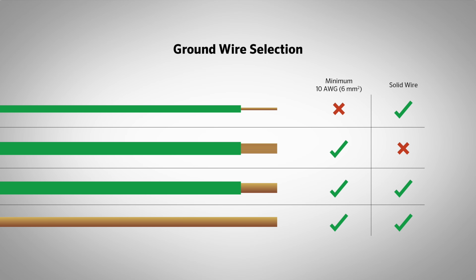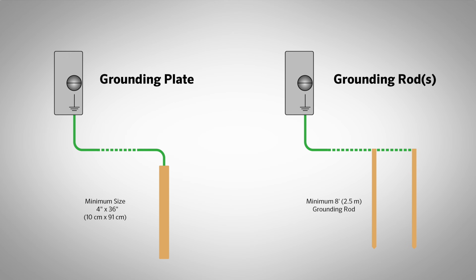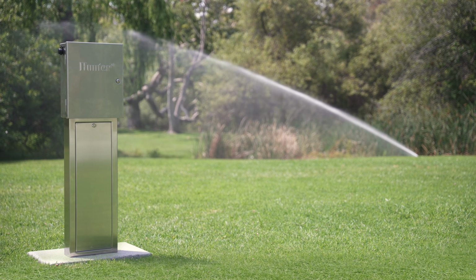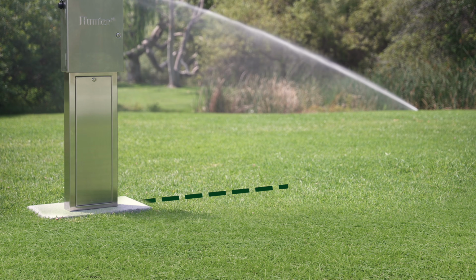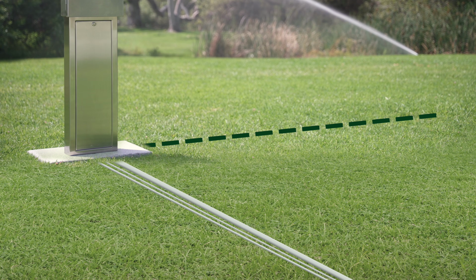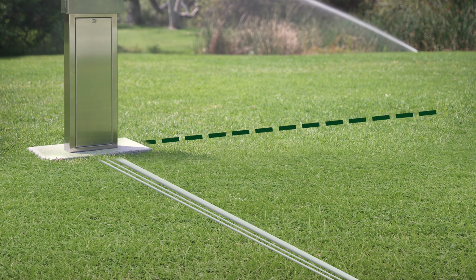to the dedicated copper ground lug, using a flathead screwdriver to tighten. Route in its own conduit and sweep to an 8-foot or 2.5 meter copper ground rod, or a copper plate at least 4 by 36 inches or 10 by 91 centimeters. Ideally, the ground wire is routed at right angles to all other field wiring connections to prevent re-entry of the surge into the controller.